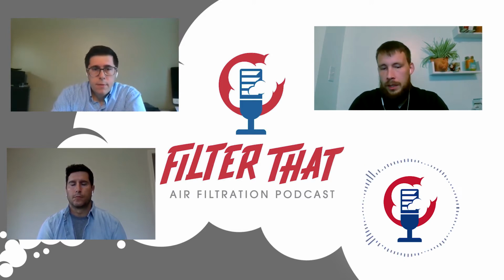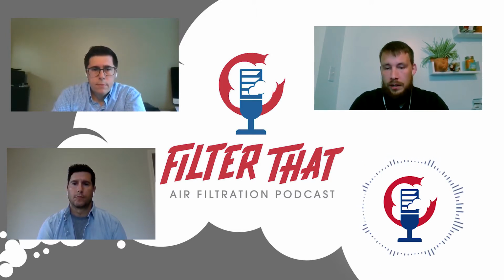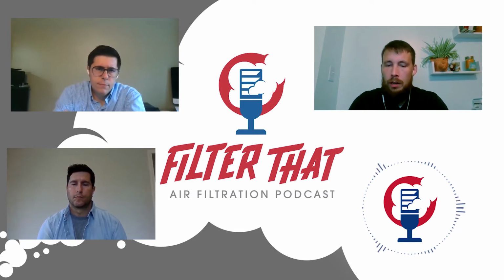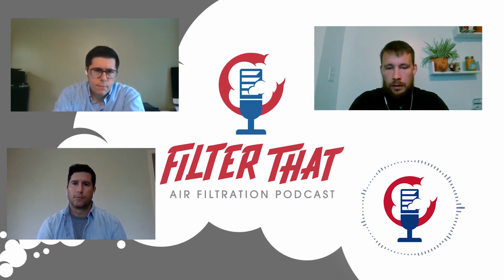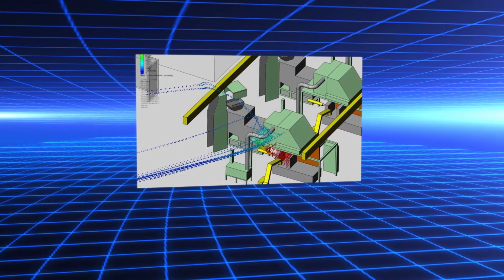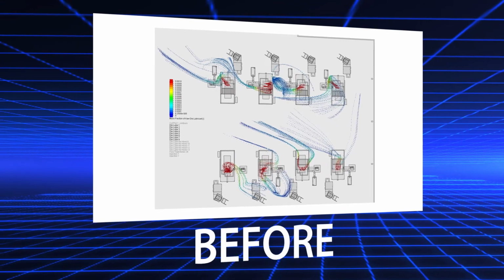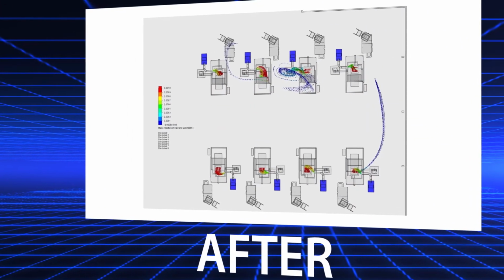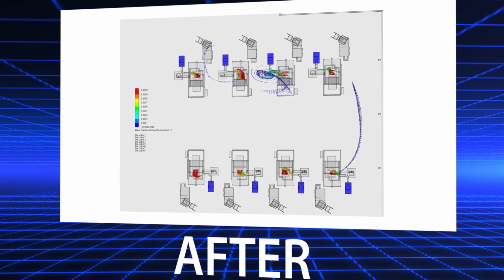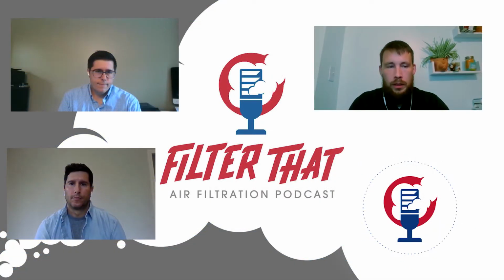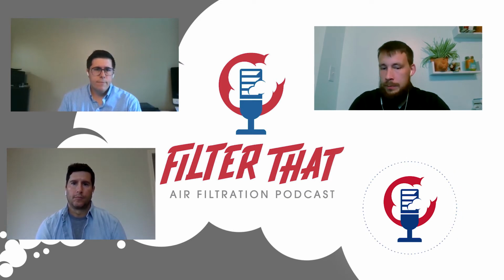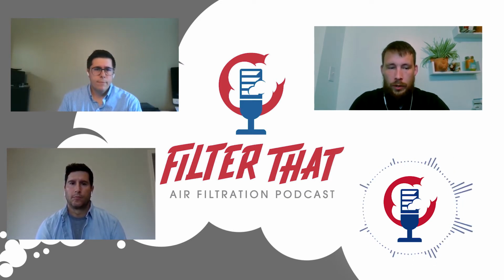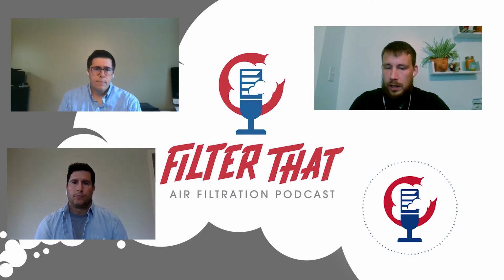So outside of that, everything's on the table: weld fume, plasma cutting, grinding, heat load studies. I recently did a heat load study for a customer where one part of their building was extremely hot and another part was much cooler, about a 10-degree difference from the northeast side to the southwest side. So we went in, took all the readings they needed, and showed them what we could do ahead of time, whether with our collectors' air conditioning package, a regular outside AC unit, or just more fresh air from outside.